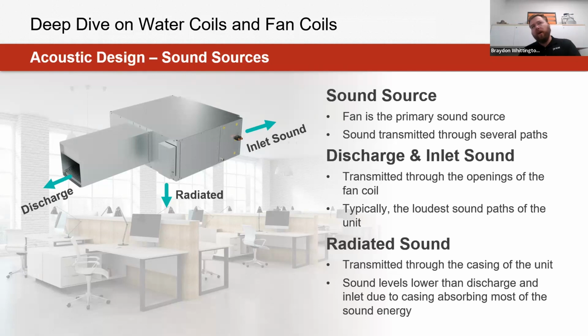So in terms of different sound sources of what you would see there too, a little bit different than a terminal unit, as you're also having inlet sound on the intake side. Essentially, if we were to look at this, discharge noise being how much noise is emitted from that fan or downstream of the product itself, radiated, the amount of noise that's being transmitted from the casing. And then now with this equipment as well, as it's typically connected to a return or ducted or even unducted applications, how much noise is then being generated or breaking out from the inlet side.